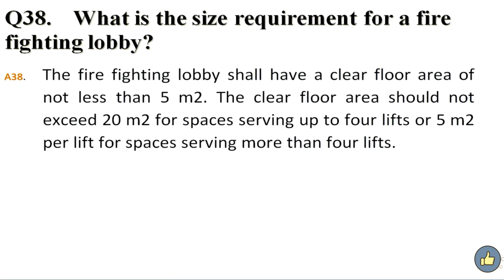What is the size requirement for a firefighting lobby? Answer. The firefighting lobby shall have a clear floor area of not less than 5 square meter. The clear floor area shall not exceed 20 square meter for spaces serving up to 4 lifts, or 5 square meter per lift for spaces serving more than 4 lifts.